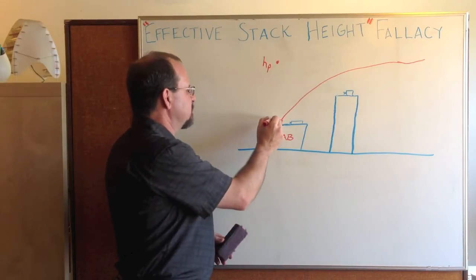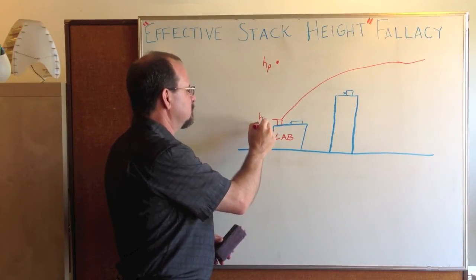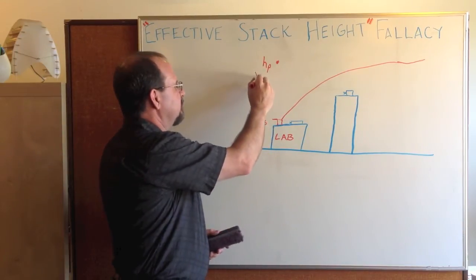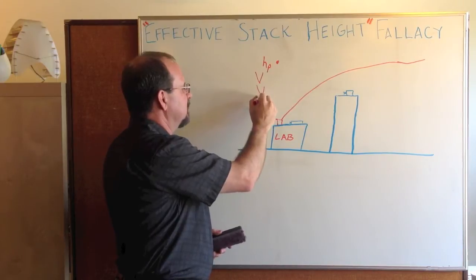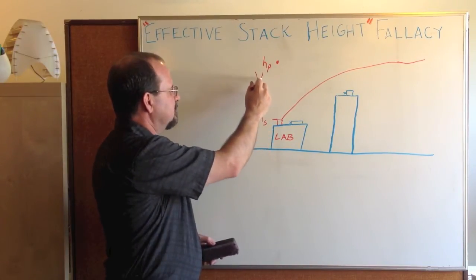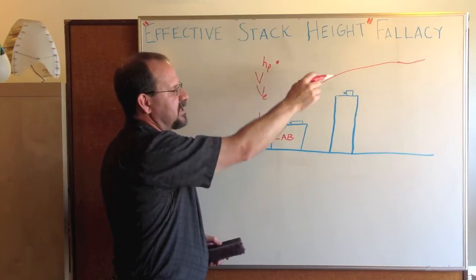The reason that's dangerous is that you have a physical stack height, and that's what you're designing. You also have volume flow rate and an exit velocity. You use your physical stack height, the flow rate, and the velocity to calculate the plume rise.